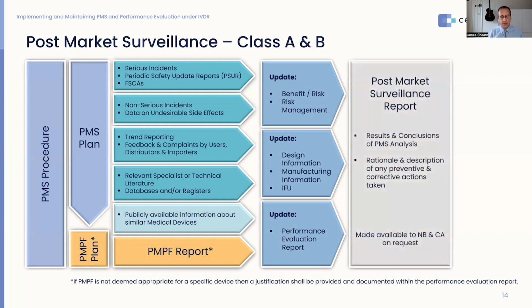For a Class A or a Class B product in the cycle, we're then required to produce a post-market surveillance report, which contains the results and conclusions of the PMS analysis and a rationale and description of any preventative and corrective actions taken under that cycle. That's made available to the competent authority on request and, if applicable, the notified body on request.